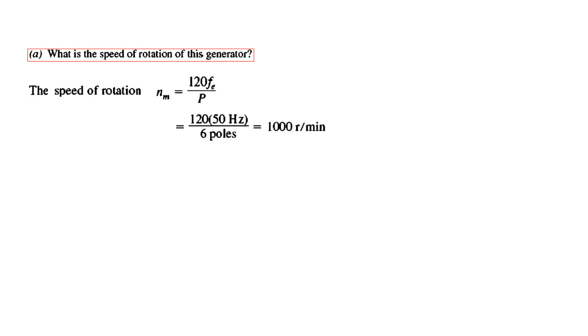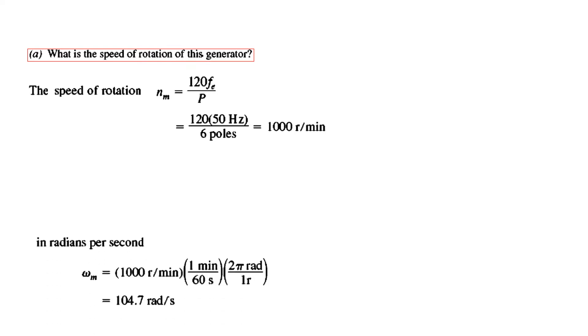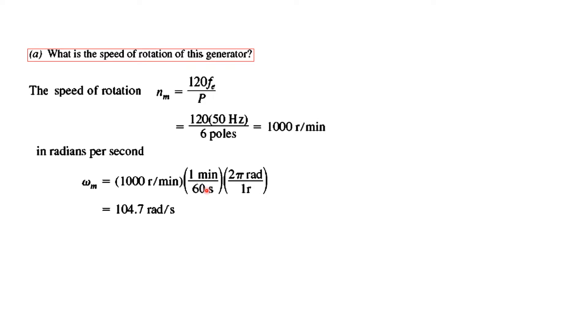Part A: What is the speed of rotation of the generator? Using Nm = 120f / P, with frequency = 50 Hz and poles = 6, the speed is 1000 RPM. We also calculate speed in radians per second by dividing by 60 and multiplying by 2π, giving 104.7 rad/s.